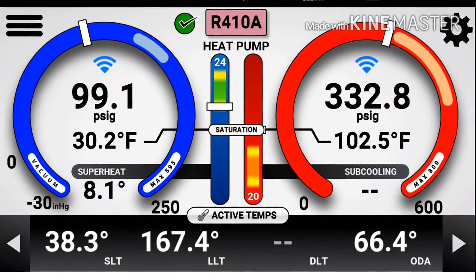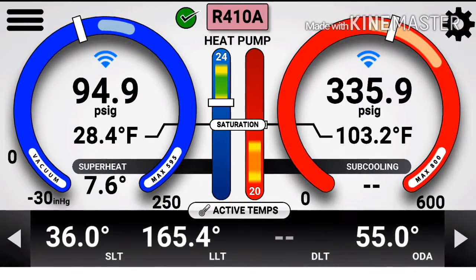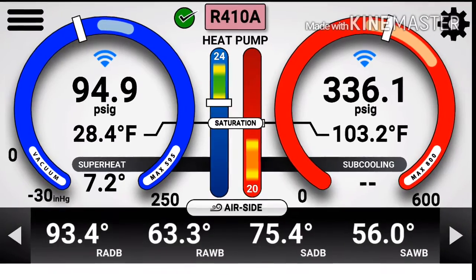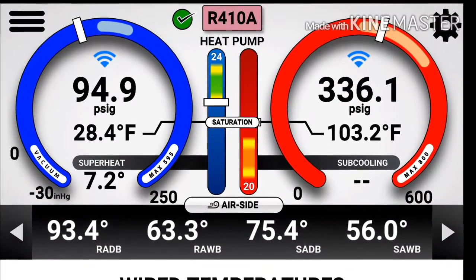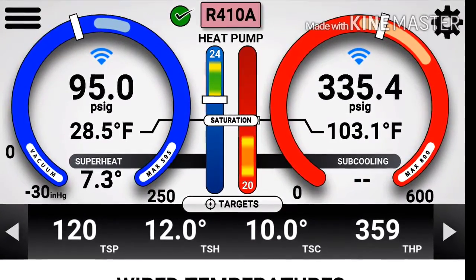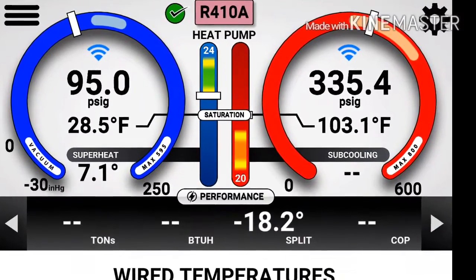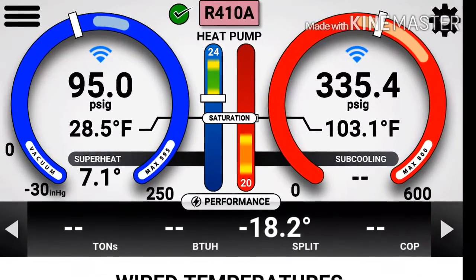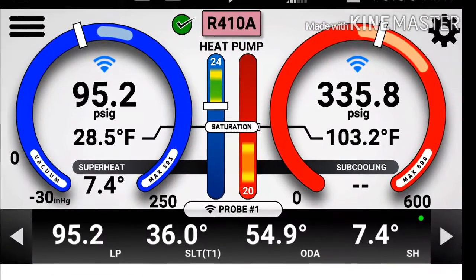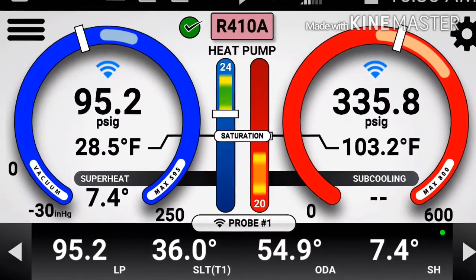Trying a voiceover here. On the screen you've got the pressures and temperatures. The outside air reading is actually the incoming water temperature. Initially the pipe was coming in kind of warm and cold — acting wacky, not the way a heat pump would. We pretty much figured out the pipes were not reversed; however, the pipes were very cold due to the incoming conditions.